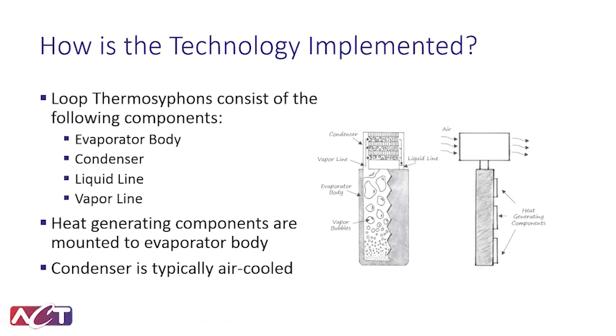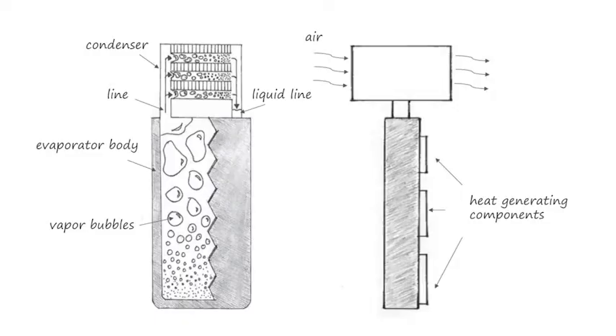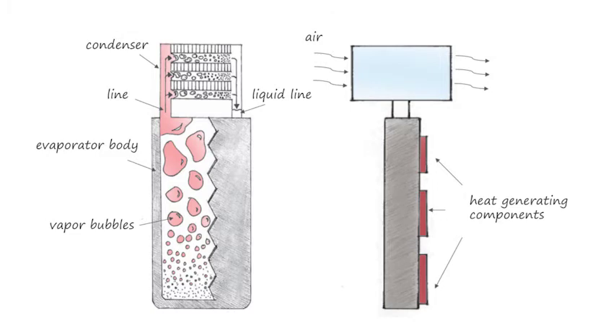You can utilize this technology in a number of ways. It consists of an evaporator, a condenser, and just two lines — one containing liquid, one containing vapor. As shown here, the configuration of the evaporator could be an aluminum plate where you mount your heat generating components like a typical liquid cold plate solution. You evaporate the fluid, it naturally rises to a tube fin type condenser. You blow air across the condenser where it condenses the vapor into liquid, falls back down, and continues the loop.